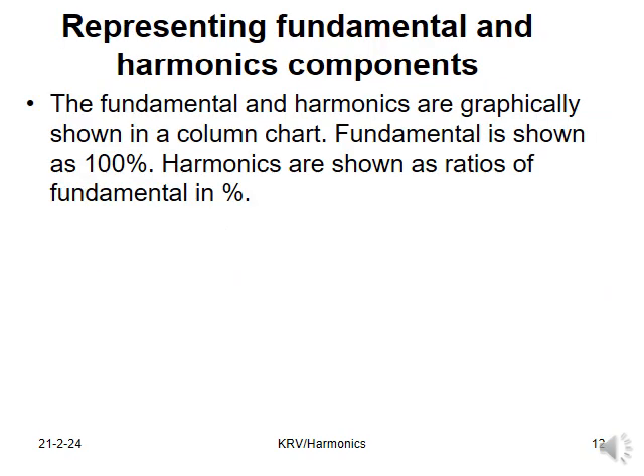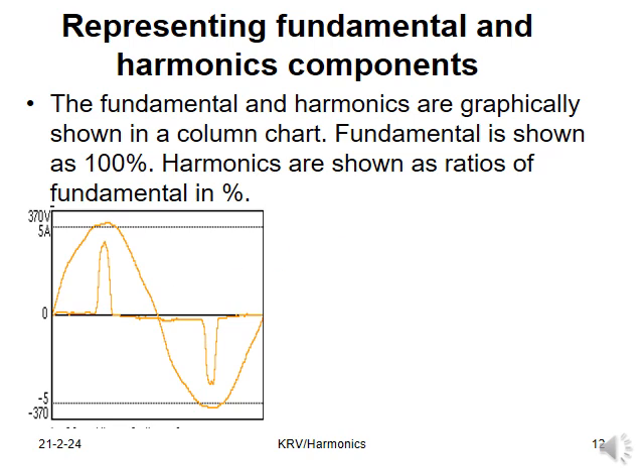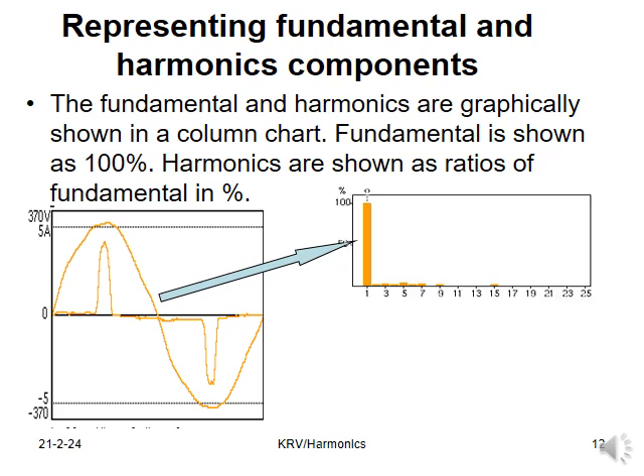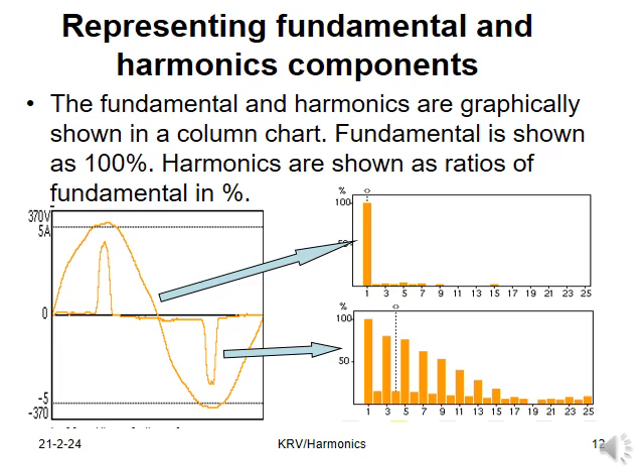The fundamental and harmonics are graphically shown in a column chart. The fundamental is shown as 100%. Harmonics are shown as ratios of the fundamental in percentage as in the diagram below. We have a sine wave which represents the supply voltage. This is resolved, and since it is a pure sine wave, it has only the fundamental component. The load current, which is distorted, when resolved has many components, namely the fundamental, second order, third order, fourth order, etc.